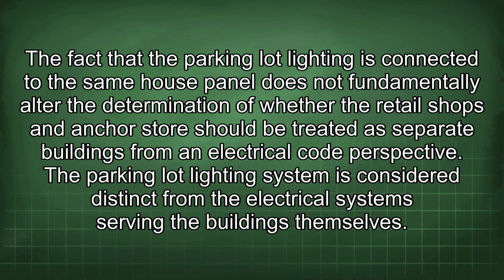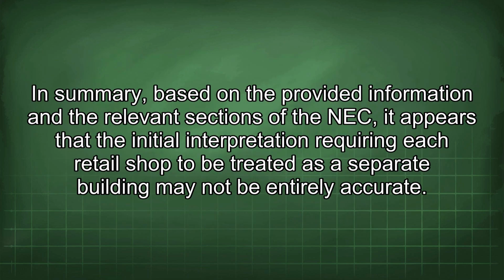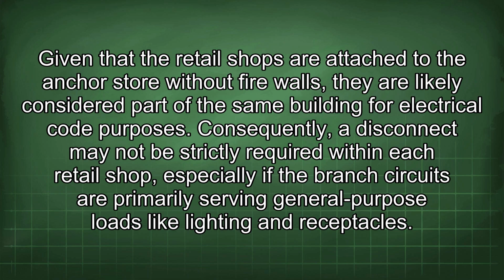circuits. The fact that the parking lot lighting is connected to the same house panel does not fundamentally alter the determination of whether the retail shops and anchor store should be treated as separate buildings from an electrical code perspective. The parking lot lighting system is considered distinct from the electrical system serving the buildings themselves. In summary, based on the provided information and the relevant sections of the NEC, it appears that the initial interpretation requiring each retail shop to be treated as a separate building may not be entirely accurate. Given that the retail shops are attached to the anchor store without fire walls, they are likely considered part of the same building for electrical code purposes. Consequently, a disconnect may not be strictly required within each retail shop, especially if the branch circuits are primarily serving general purpose loads like lighting and receptacles.